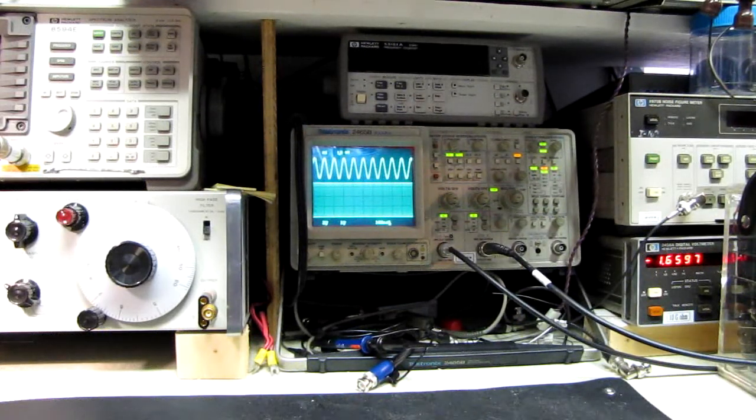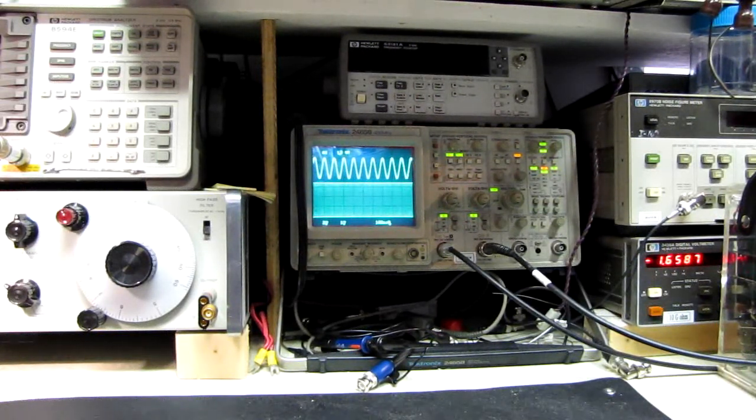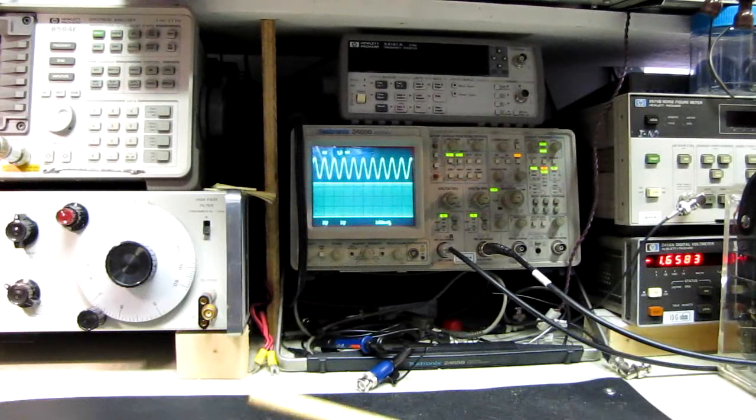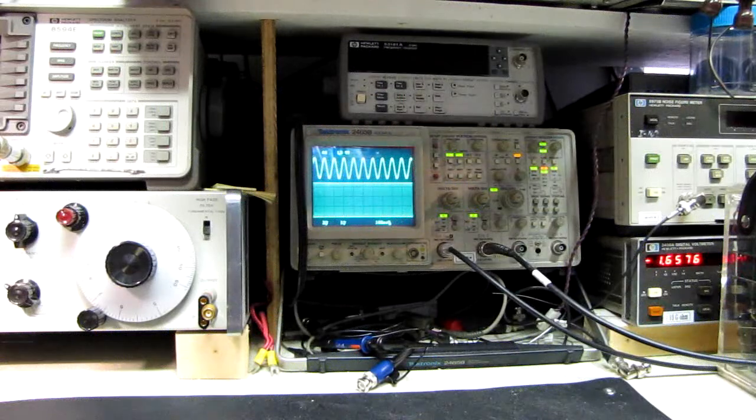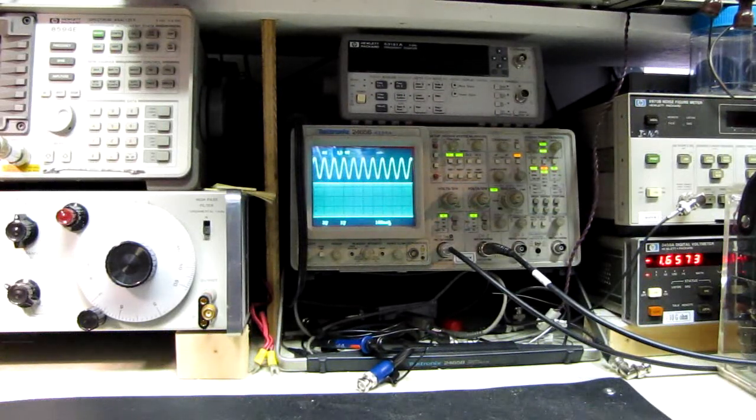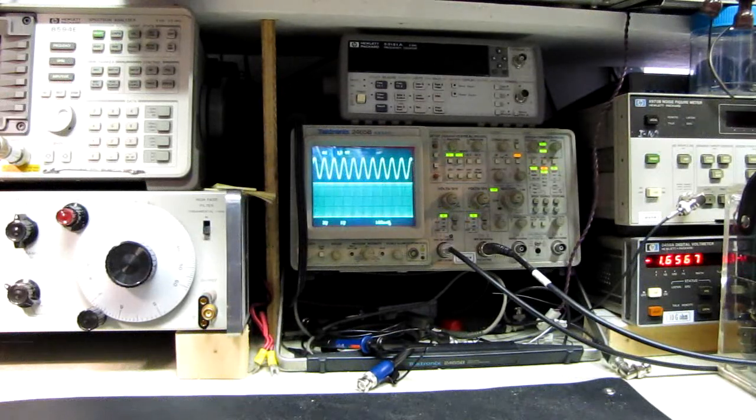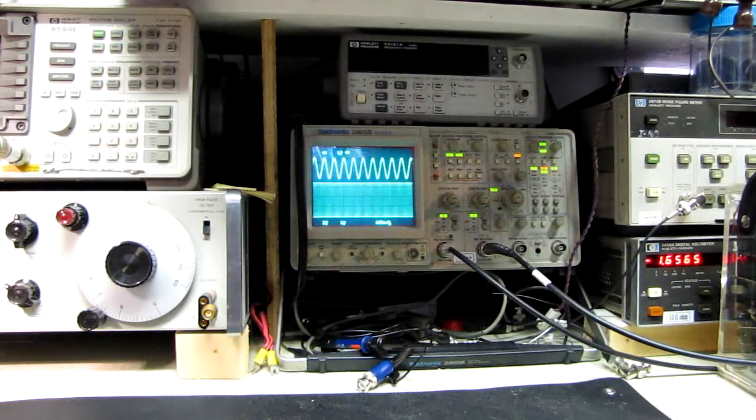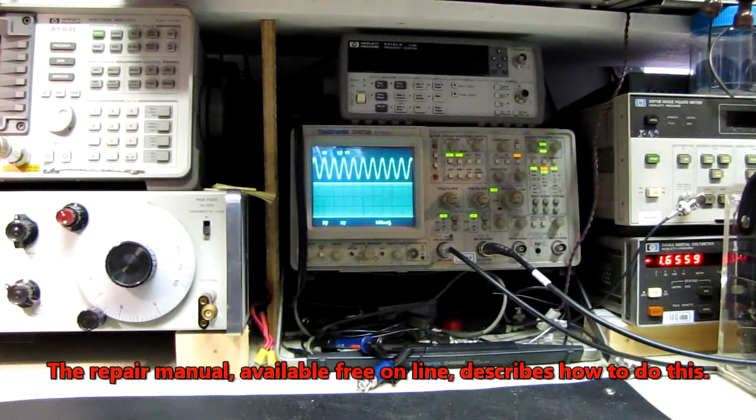And again, it has to come up to temperature and it won't be at full stability for a couple of hours. Now the rubidiums are good. The problem was my rubidium standard turned out to be about 10 hertz off, and I actually had to go inside and change a resistor to bring that back into spec before I could trim it back into spec. It had drifted far enough out of spec.